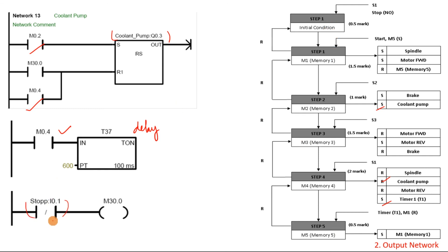The stop button, which is a normally closed momentary switch, will turn on M30. That is why in the previous networks you can see M30 being fed to the reset part of every step and output network. That is all for the step sequence transformation into a ladder logic diagram using the reset and set function. Remember, there are two networks: the first is the step sequence network covering the movement from initial condition to the end of the steps, and the second is the output network which translates all the output conditions for each actuator. I will see you again in the next chapter.